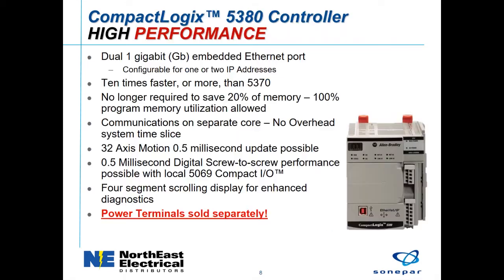The CompactLogix 5380 controller was released in the summer of 2016. It's a high-performance controller. It offers a dual gigabit embedded Ethernet port, and that's configurable for 1 or 2 IP addresses. In general, it executes code 10 times faster or more than the 5370 series of controllers, the previous generation. And it no longer requires you to save 20% of user memory for system overhead. You can now use up to 100% of the memory available for the program.